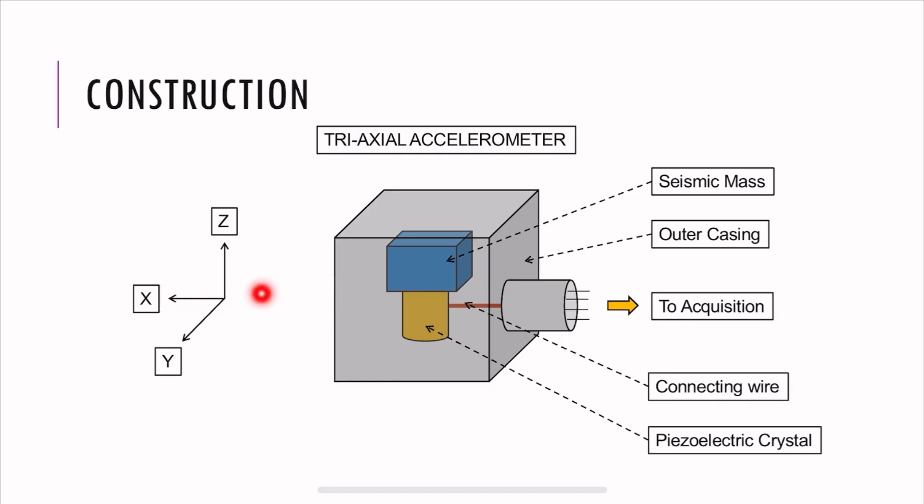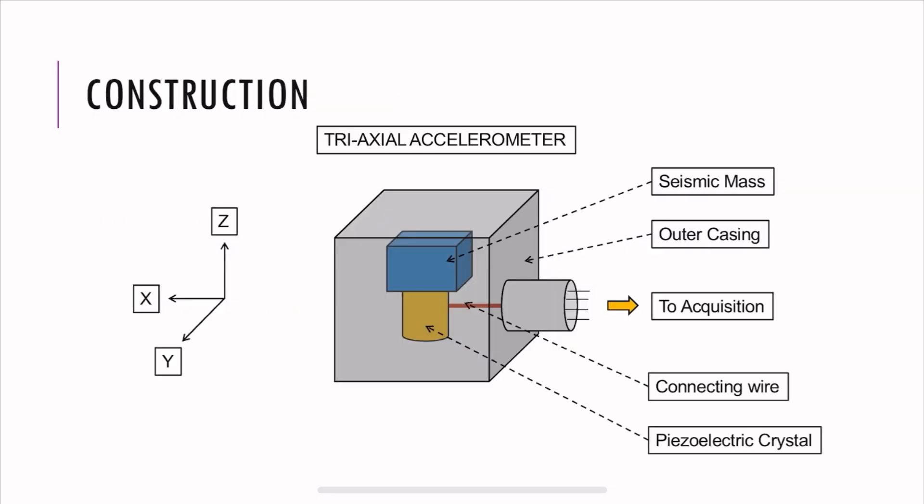Now let's talk about the working principle. When you're connecting the accelerometer and it's actually measuring vibrations, it's experiencing load. The seismic mass causes stress on the sensing piezoelectric crystals. So in response to this load, the piezoelectric crystals generate an electrical output. This output is collected and transmitted by wires to the data acquisition system.